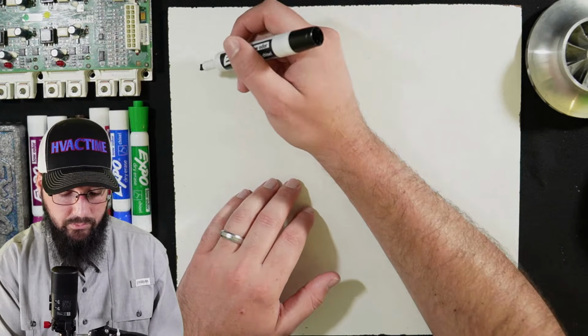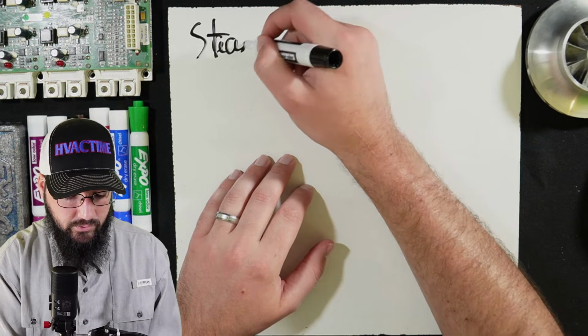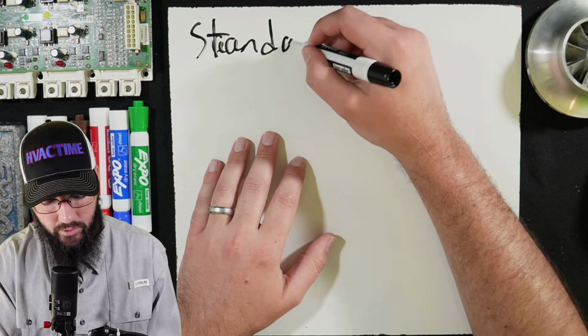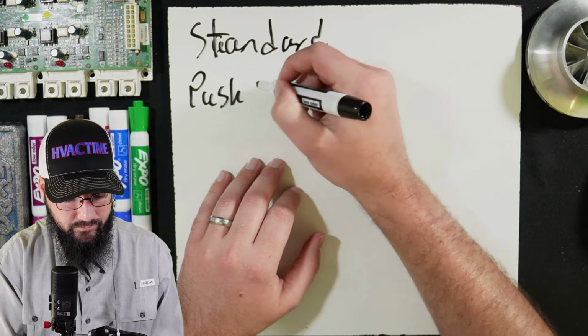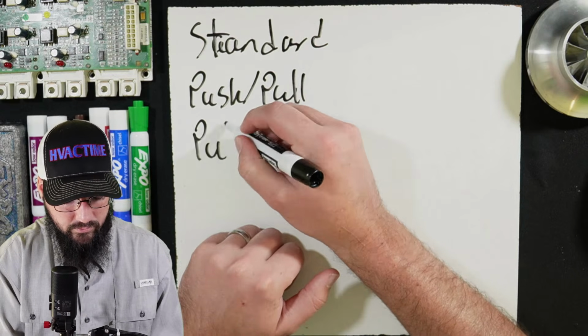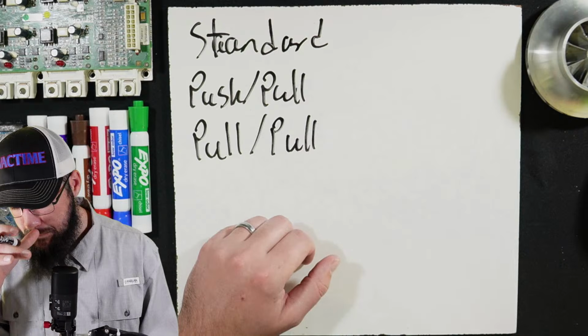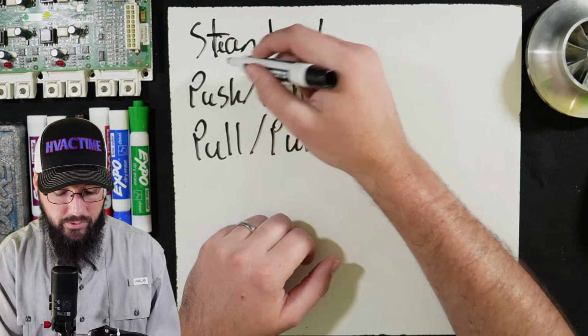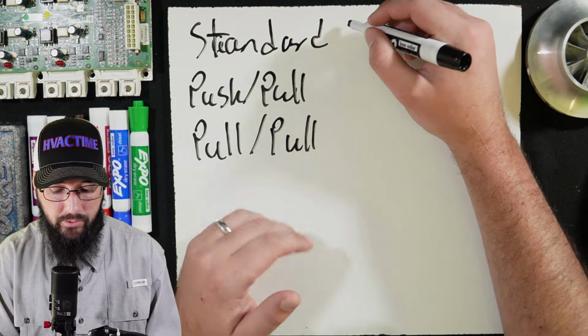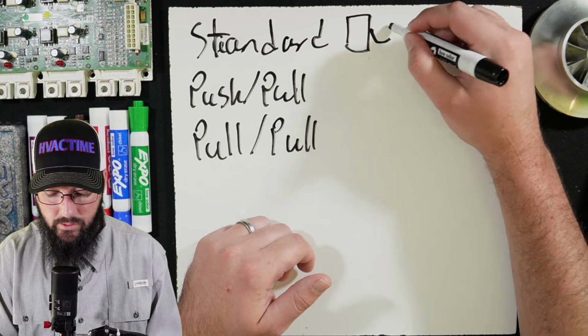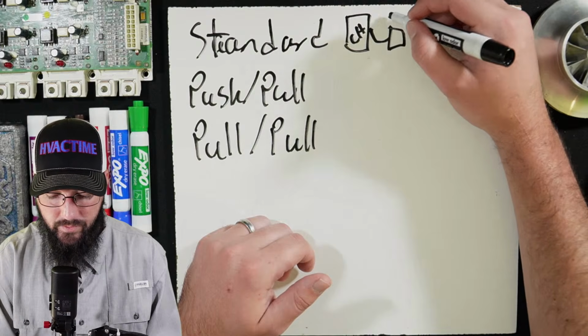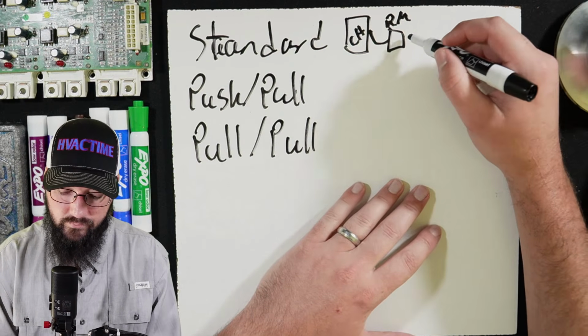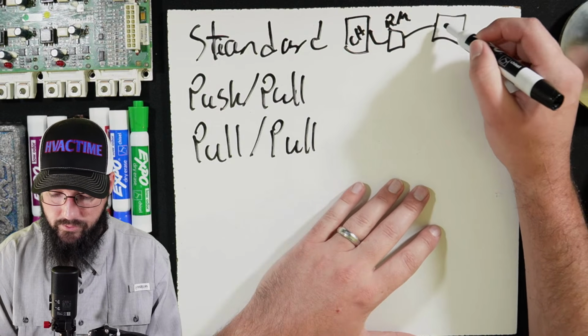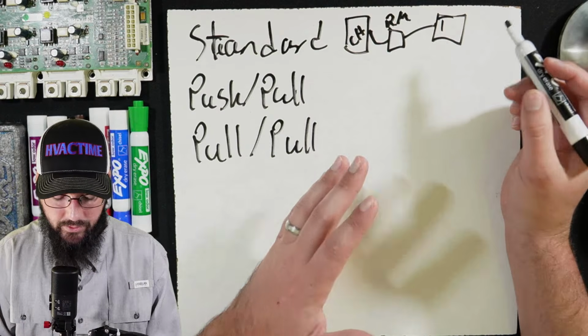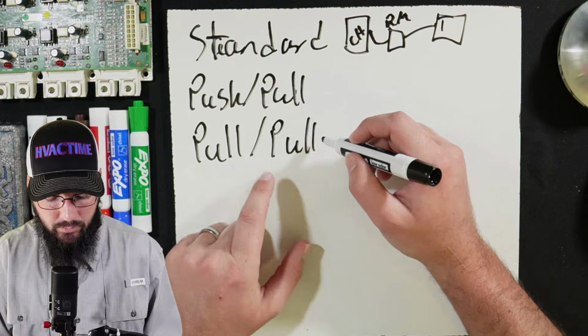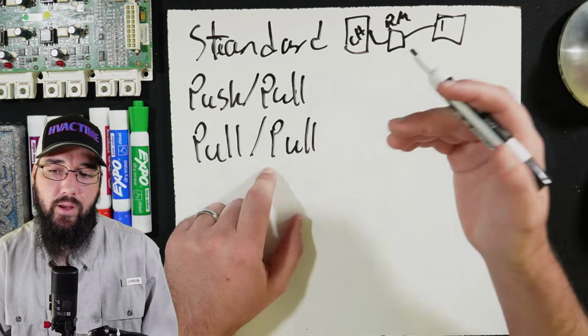let's first define some of the methods we have. So we have a standard recovery. Let's just get on the same page with our definitions. We have standard, push-pull, and then pull-pull. The standard is just what you would always expect, right? We're coming straight out of the machine into our recovery machine. Let's say this is our chiller. Call this a recovery machine, and then we push that into our cylinder or our tank. We'll just call that T for tank. Standard recovery.